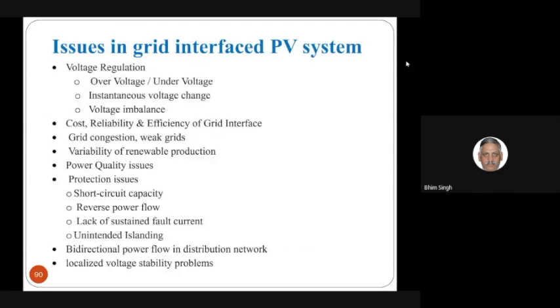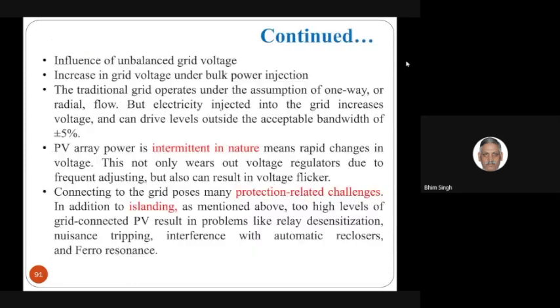So now coming to the issues in grid interface PV systems, one problem in the Indian grid is the major problem of over voltage and under voltage. The first plant I remember, a decade before, was by Bhel Power in Moradabad on an 11 kV substation where the voltage was fluctuating from 9 kV to 13 kV, and that's the reason the inverter was tripping very frequently. Another is instantaneous voltage change and voltage unbalance, the cost, reliability and efficiency of the grid interface, grid congestion and weak grid. So we have a very poor, weak grid, and variability of renewable production and power quality issues like protection issues: short circuit levels, reverse power flow, lack of sustained fault current, unintentional islanding, bidirectional power flow in the distribution network, and localized voltage stability.